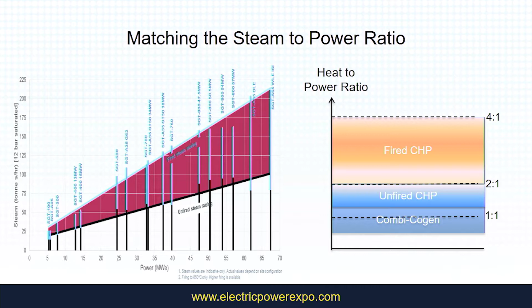We looked at the traditional heat match and we looked at this combi cogen type match, and you can see you're saving somewhere just over £1 million a year on your operating costs by going through the combi cogen, simply because the electricity is so expensive. It's 5 times the cost of gas on a pounds per megawatt hour basis. And there's just a chart showing if you've got a little turbine, you can fire it to get a lot more steam than you would normally have. And looking at the sort of heat to power ratios, combi cogens around 1 to 1, traditional gas turbine CHP somewhere around 1.5 to 2 to 1, and your fired CHPs up to as much as 4 to 1 heat to power ratios. Now, the other thing is fuel flexibility can have a huge benefit as well.